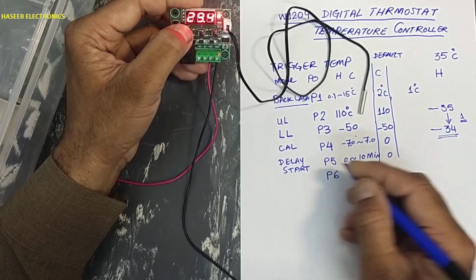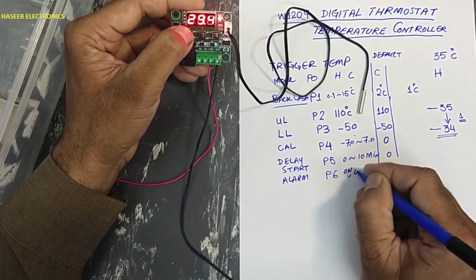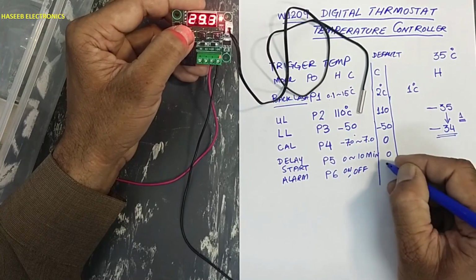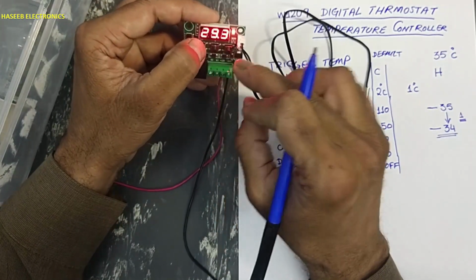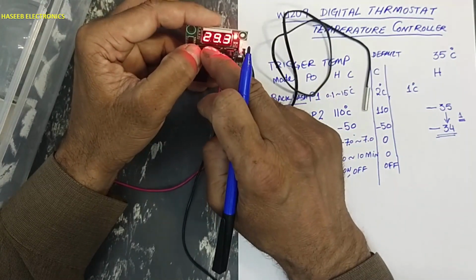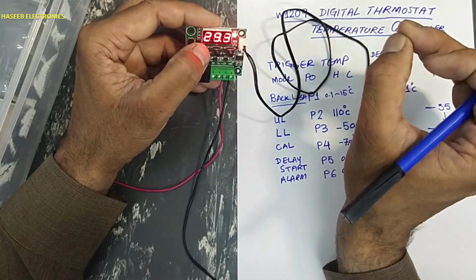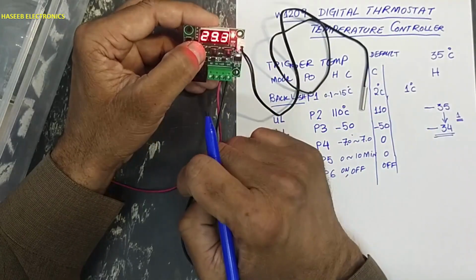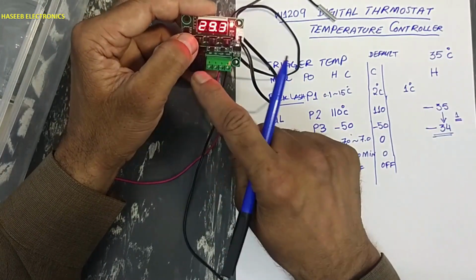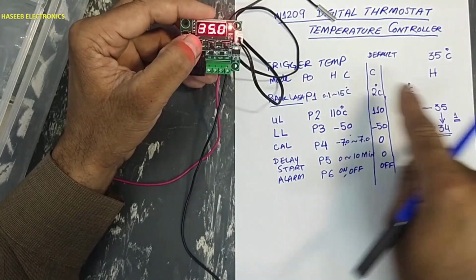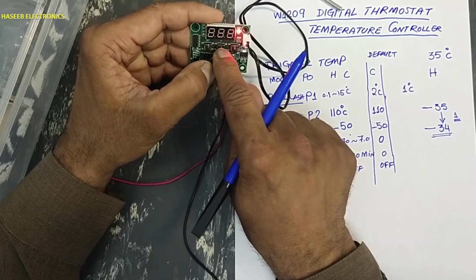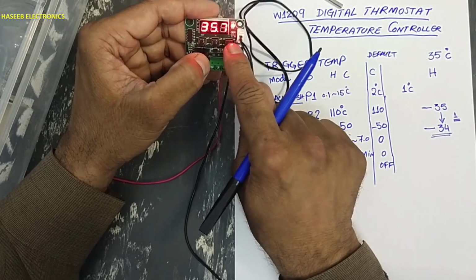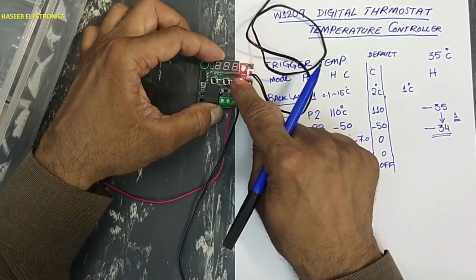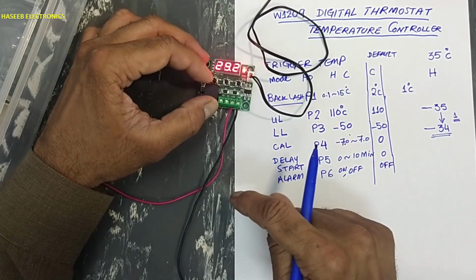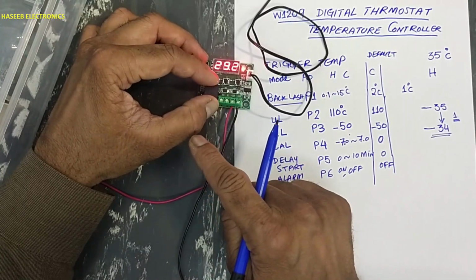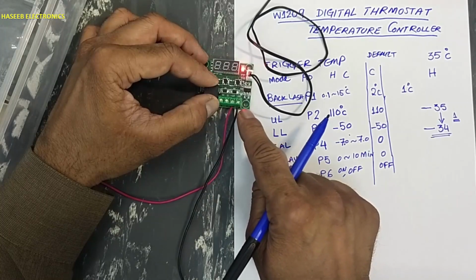Then P6. That is alarm. On, off. The default setting is off. We can set any borderline. At that time it will give 3 dashes and it will indicate that the temperature is in any dangerous limit. Let's make setting this one. First set flashing 35, okay, 35 degree. We can increase the temperature with 0.1 degree centigrade increment, or we can decrease the temperature with 0.1 increment. 35 degrees. Set. Value is stored. Press set button again and keep pressed.